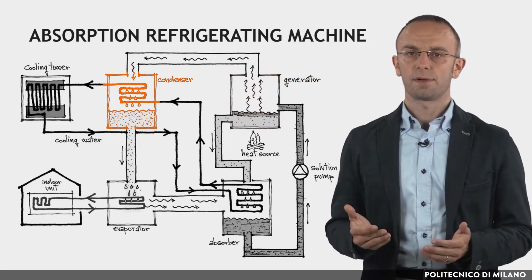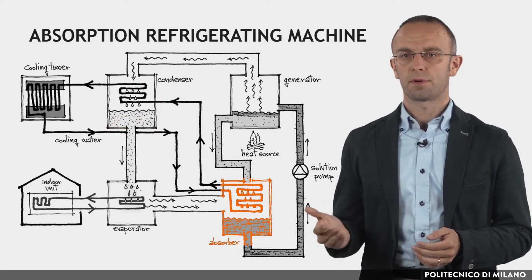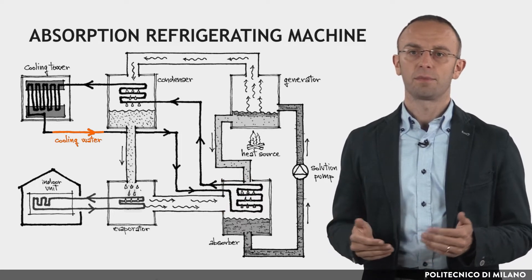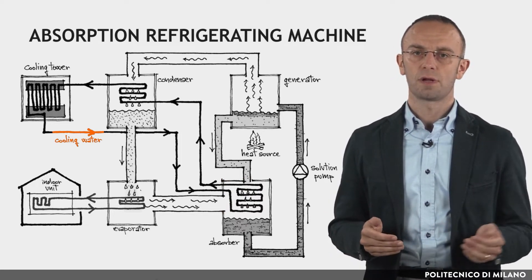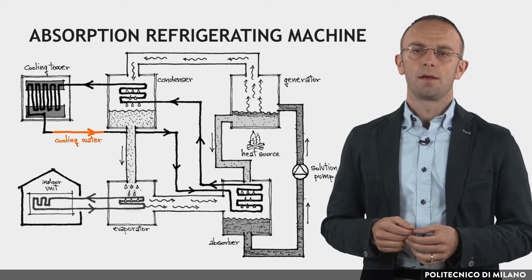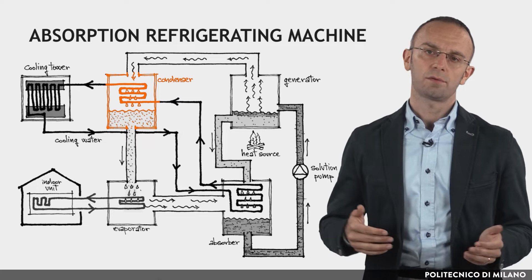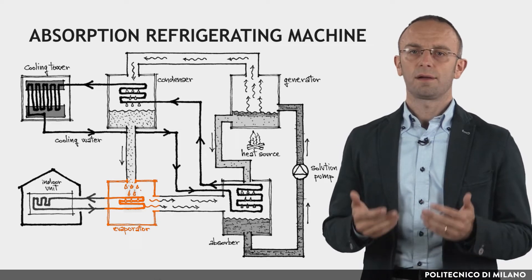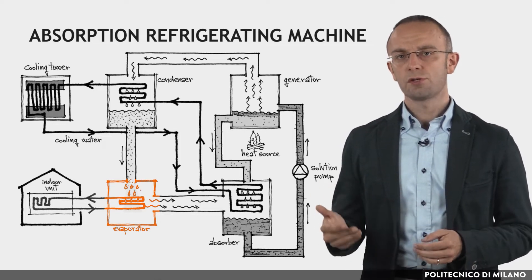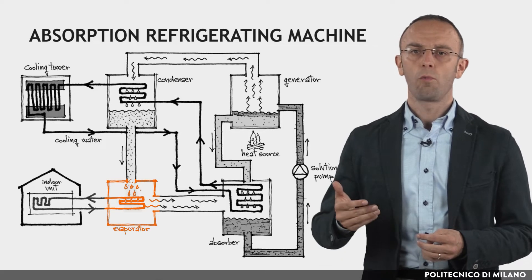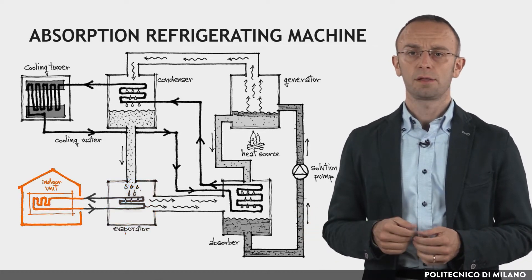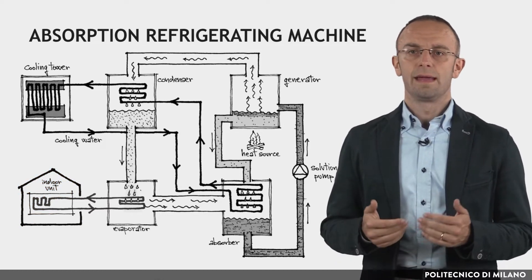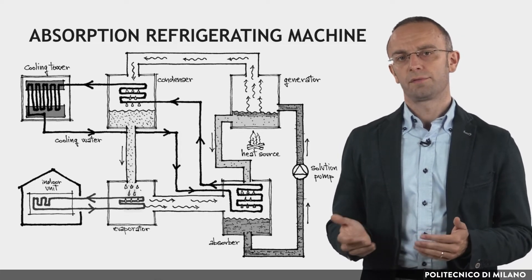The remaining concentrated part of the solution flows down into the absorber chamber. In the condenser, the cooling water absorbs the condensation heat from the vaporized part of the solution, changing it into a liquid. The liquid refrigerant flows from the condenser to the evaporator, experiences a drop in pressure and temperature, and is sprayed on a heat exchanger through which the water to be chilled flows before reaching the indoor unit. The efficiency of the absorption machine is dependent on the temperature of the heat source — the higher the temperature, the higher the efficiency.